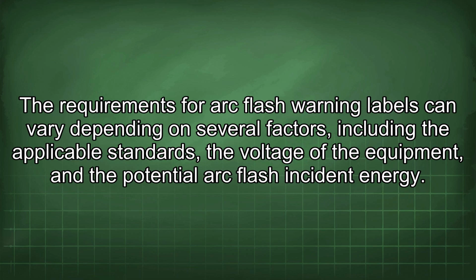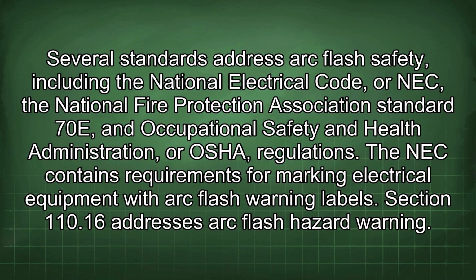The requirements for arc flash warning labels can vary depending on several factors, including the applicable standards, the voltage of the equipment, and the potential arc flash incident energy. Several standards address arc flash safety, including the National Electrical Code, or NEC, the National Fire Protection Association Standard 70E, and Occupational Safety and Health Administration, or OSHA, regulations.